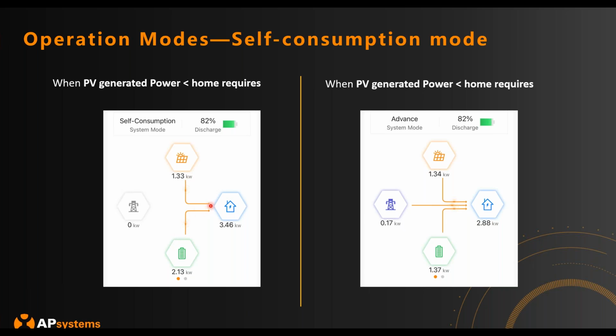But say it's nighttime, there's no solar at all, and the home is using 3 kilowatts. The battery will continue powering the home because self-consumption mode means I don't want to use the grid as much as I can - I want to use batteries and solar. The battery keeps pushing power to the home until it hits a programmable threshold, say 50% state of charge. Once it hits that, the battery stops discharging and the home has no choice but to pull power from the utility.